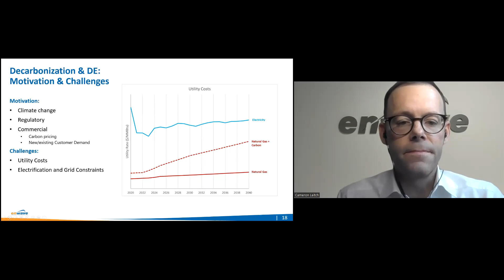Although the graph shown here is a representative forecast for utility costs in Ontario, fossil fuel-based energy prices are commonly lower than electricity on a dollar per unit energy basis. In Ontario, electricity is currently 4 to 5 times the base cost of natural gas, using a blended cost for electrical demand and consumption. With the introduction of increased carbon pricing, the gap is closed substantially, but it appears likely that natural gas will remain at a lower cost well into the future. In addition, having the ambition to decarbonize by switching from fossil fuels to electricity doesn't mean that the electrical utility will be able to accommodate. Most electrical grids are constrained, or they would become significantly constrained through the rapid electrification of heating systems. Next slide, please.